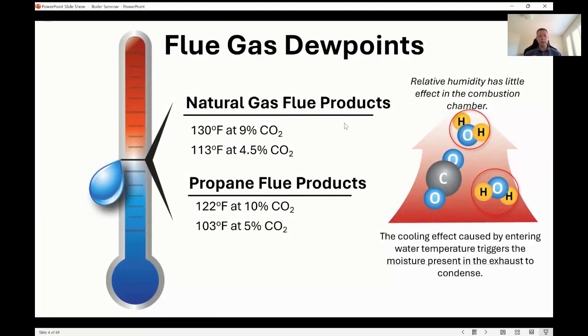What you're doing with condensing boilers is getting below the dew point, where that water vapor will condense from a gas into a liquid. And when you do that, it releases energy. That energy gets put back into your thermal balance, and that's how you get the higher efficiencies from a condensing boiler. Now, the dew point of natural gas will vary depending on the type of fuel you're using and the type of combustion that you have.